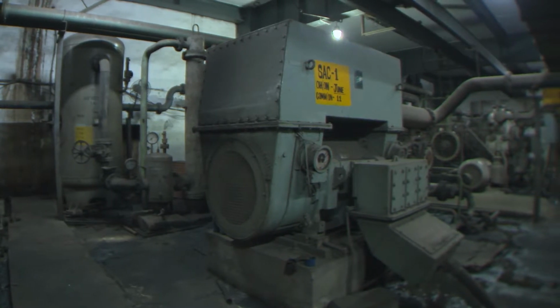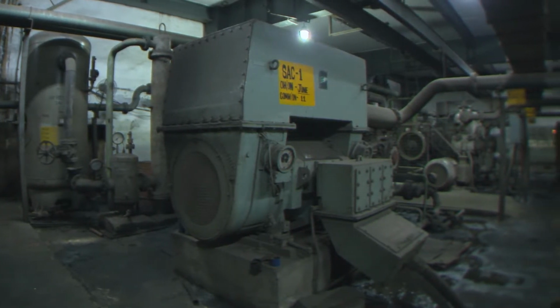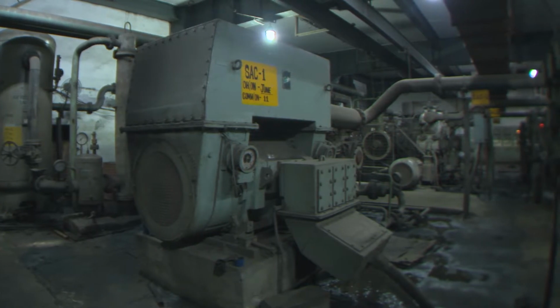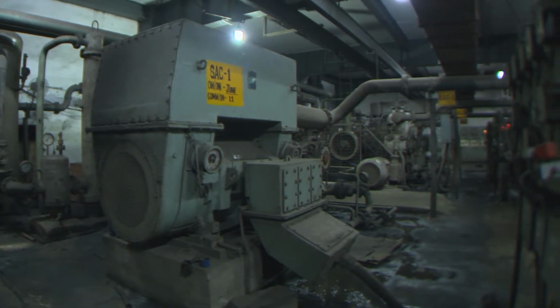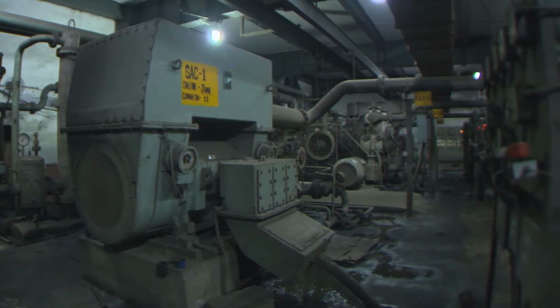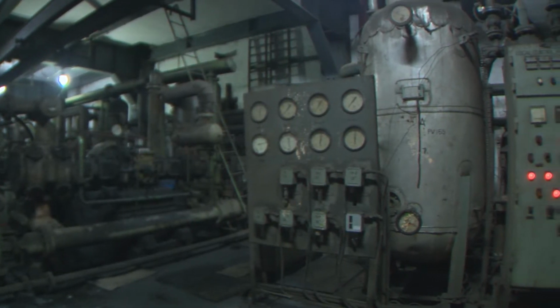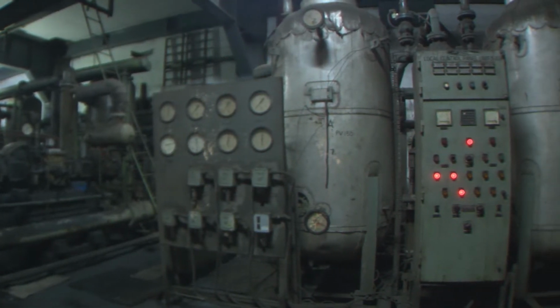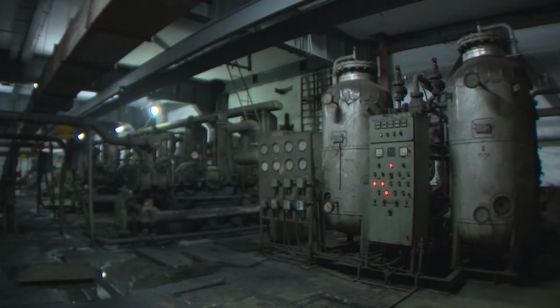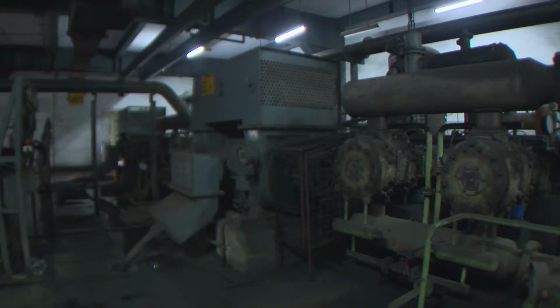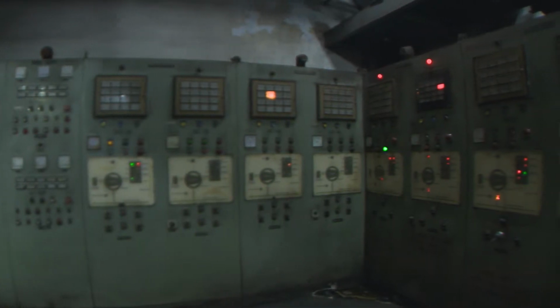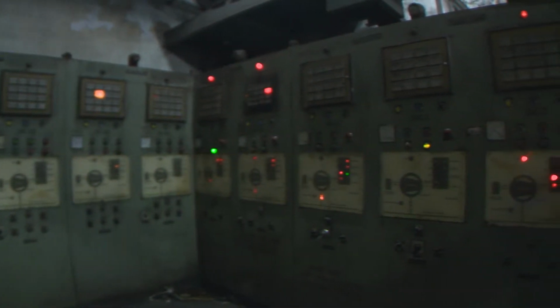Air compressor system. Service air compressor supplies air with 8 kg per centimeter square pressure for cleaning the equipment, floors, etc. during maintenance work. Instrument air compressor supplies air through air dryers. The air is used for actuating all pneumatically operated control valves, control air dampers and pitch control mechanisms of ID fans and FD fans.